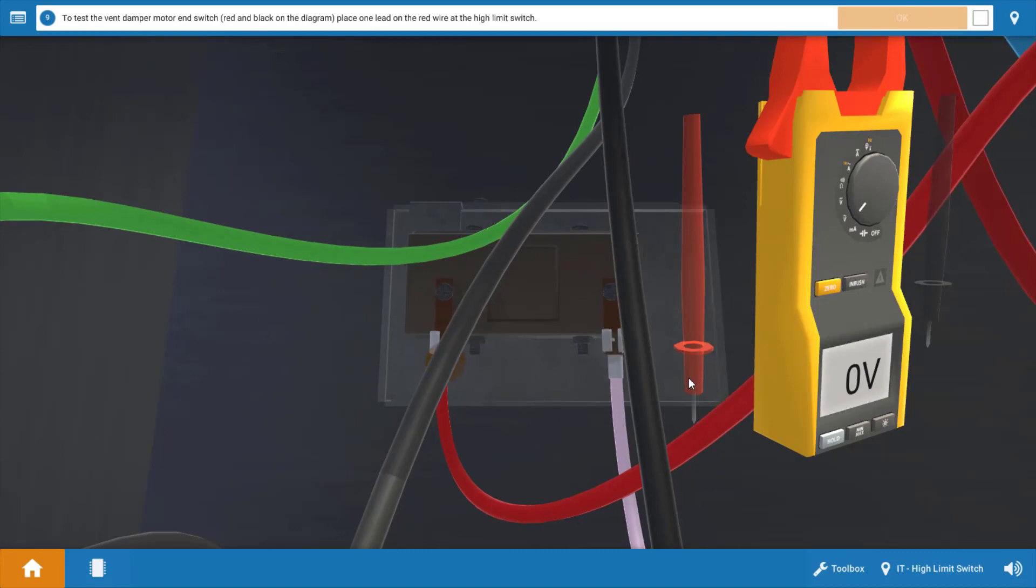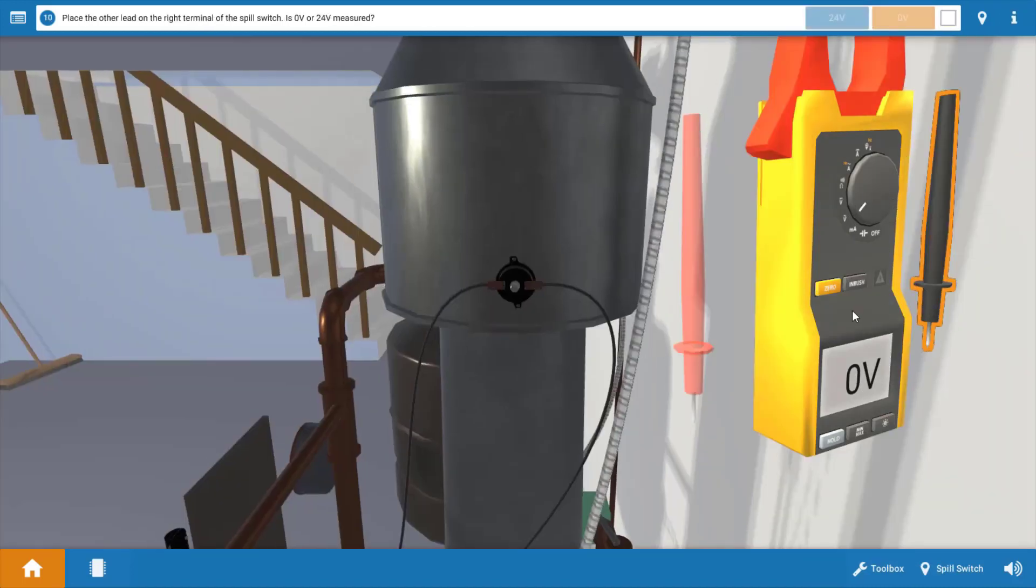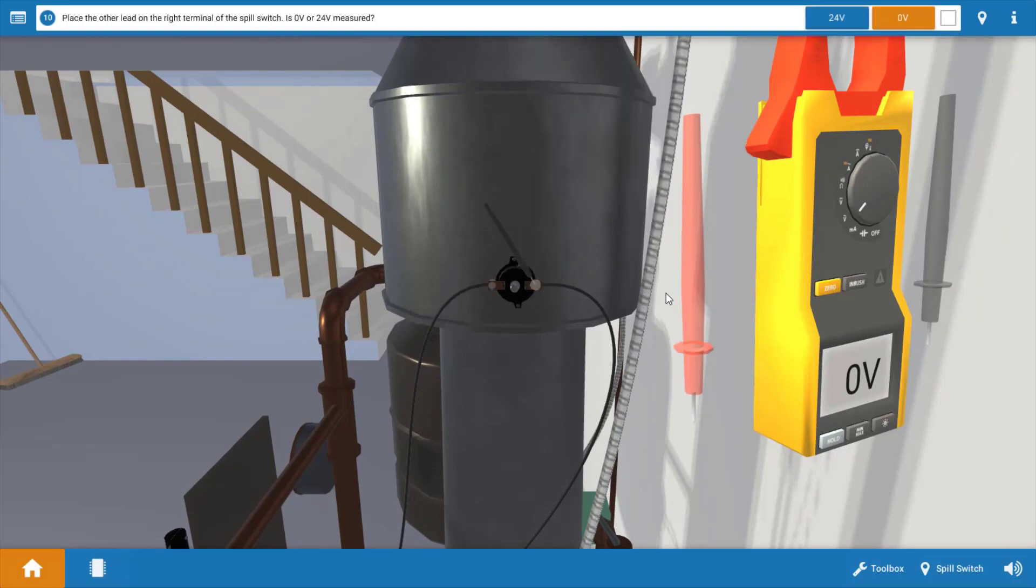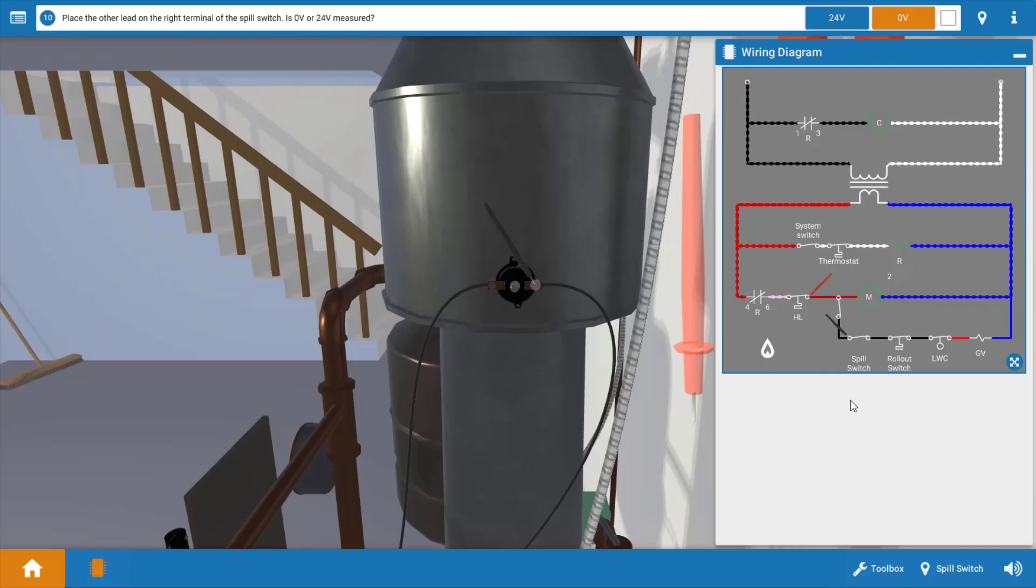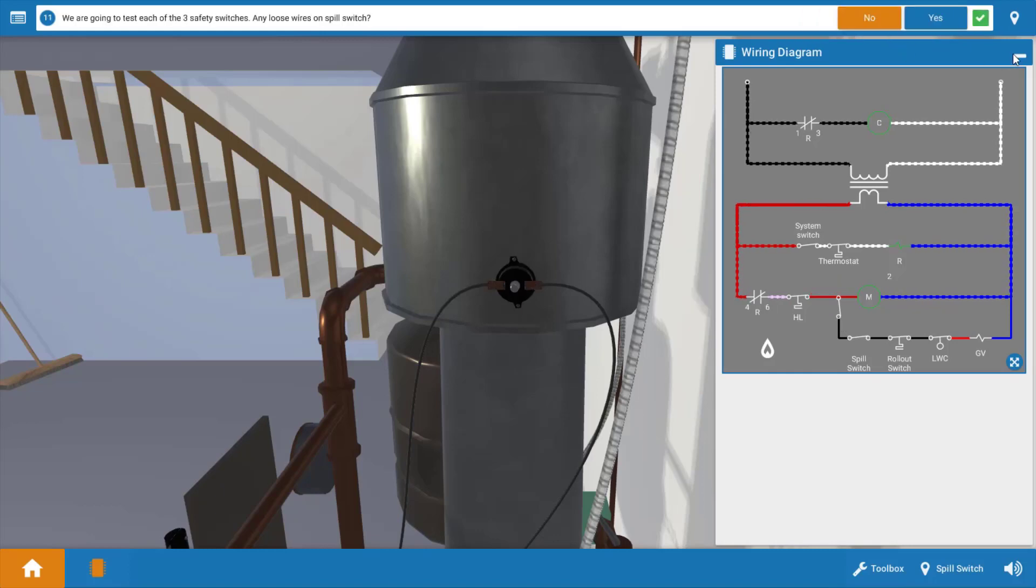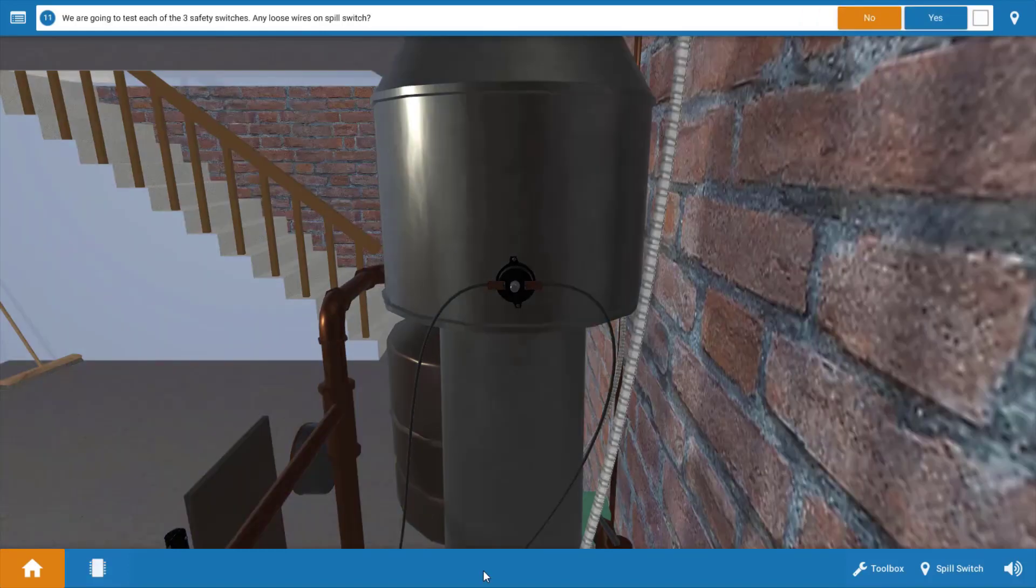We're going to place one of our leads at the connection on the high limit here on the glowing orange hot spot. Our black lead is going to be placed at the right side of the spill switch. Now we have zero volts here. Let's take the wiring diagram out and we'll be able to see the placement of the meter leads. We can see here that the meter leads are placed directly across the proving switch or end switch within the vent damper. Because it's showing zero volts this verifies there's no difference in potential across that switch and the switch is closed. There's no direct connection to measure voltage on the vent damper end switch, so we've got to do it at these two locations. Now that we've verified that the vent damper proving switch is closed, this leads us to one of these three safety switches as our culprit.